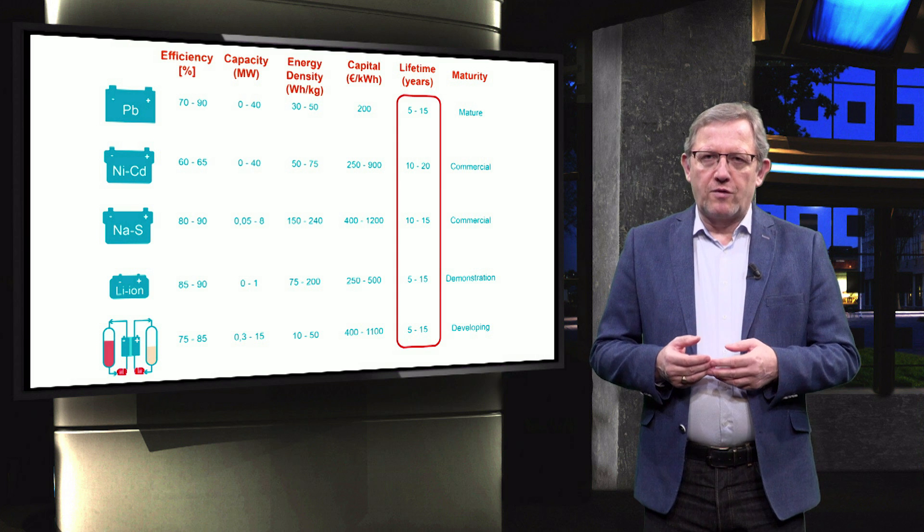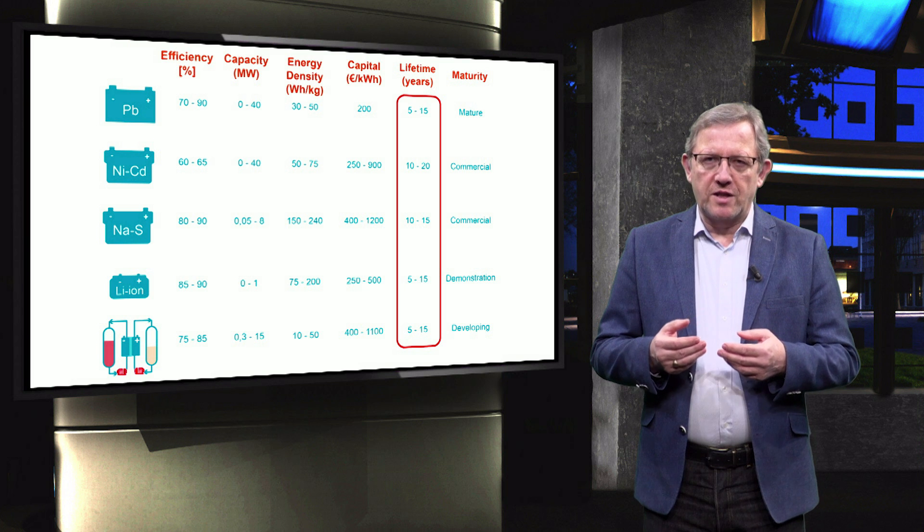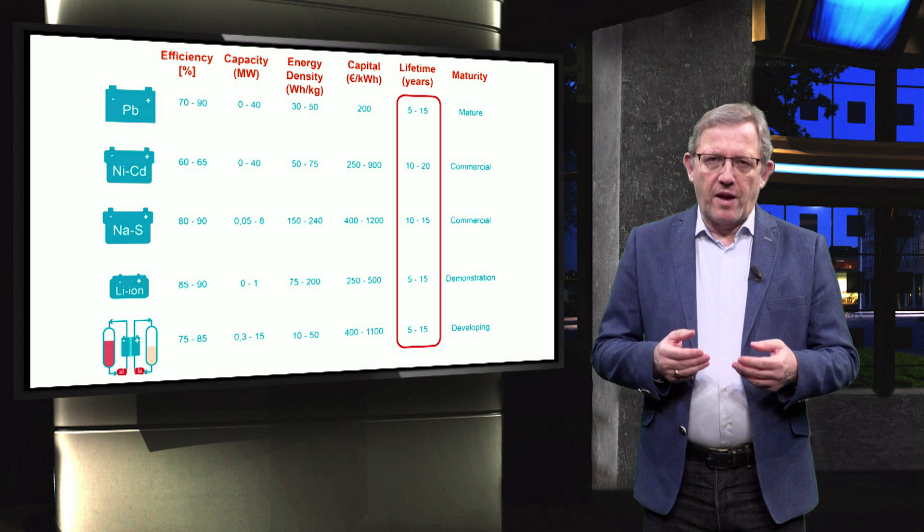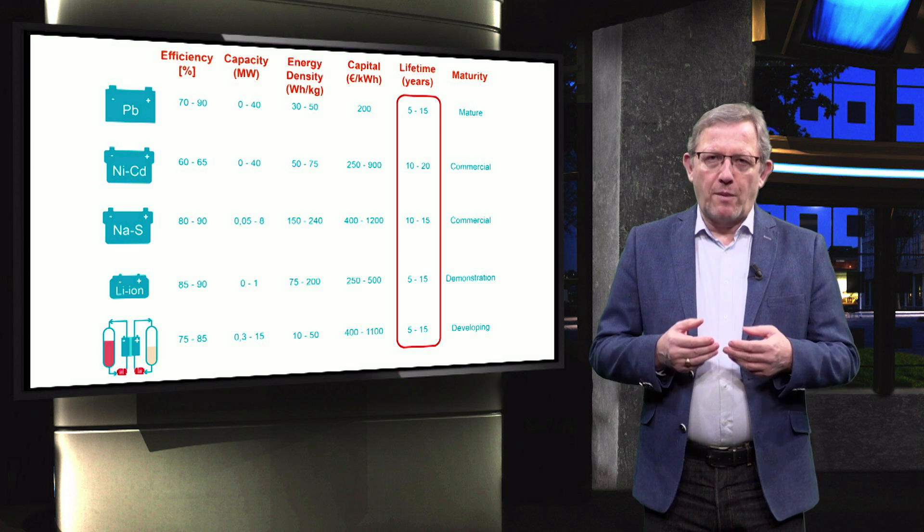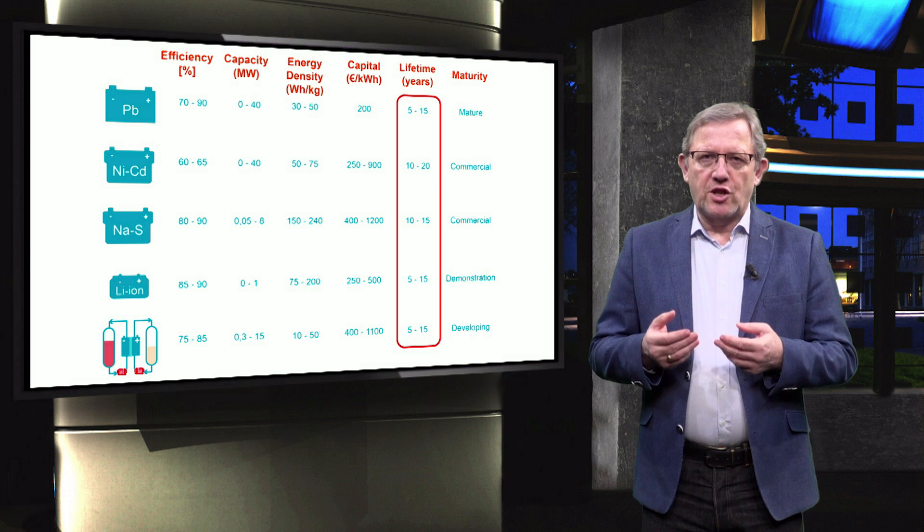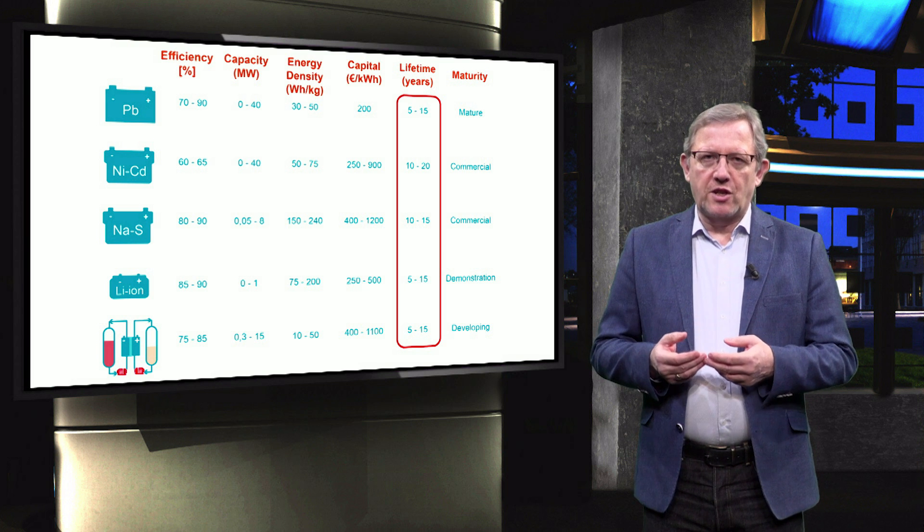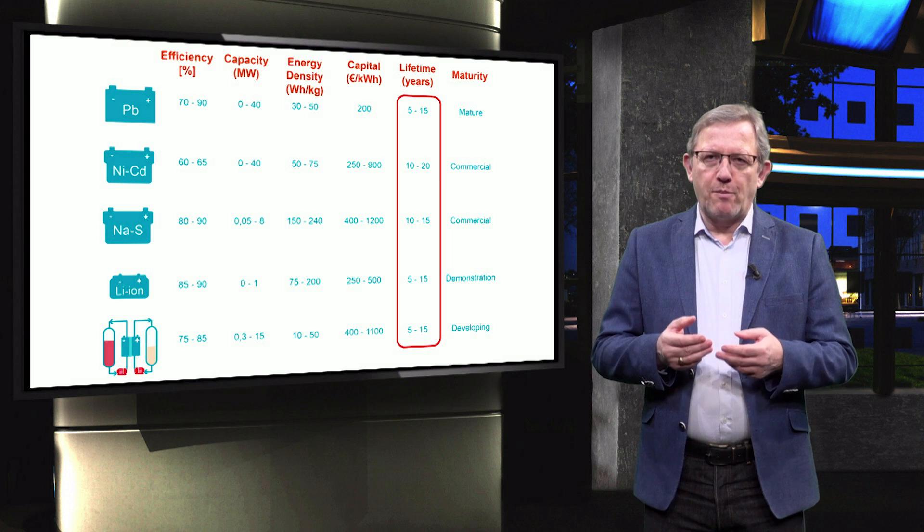The lifetime of these batteries depends on the type of services they provide, ranging from 5 to 15 years, depending on number of cycles, depth of discharge and many other parameters such as C-rate, charge and discharge rate and temperature.